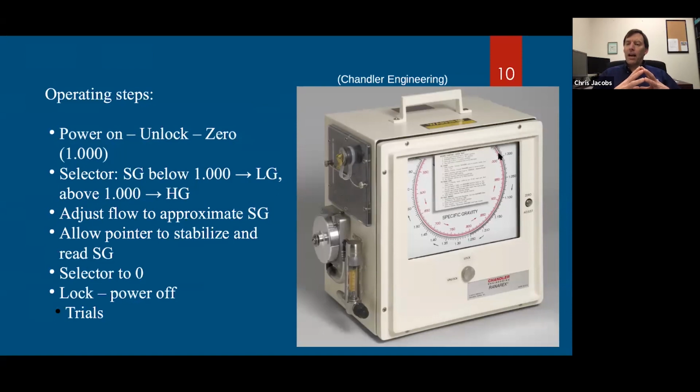Now, it will take some time to do that because we talked about how the gas coming in has to impinge on the impulse wheel. So it takes some time for that to build up to a normal operating speed. The impellers are operating at a fixed speed, but to transfer that energy over to the impulse wheels will take a few seconds. The chambers have to fill with air.